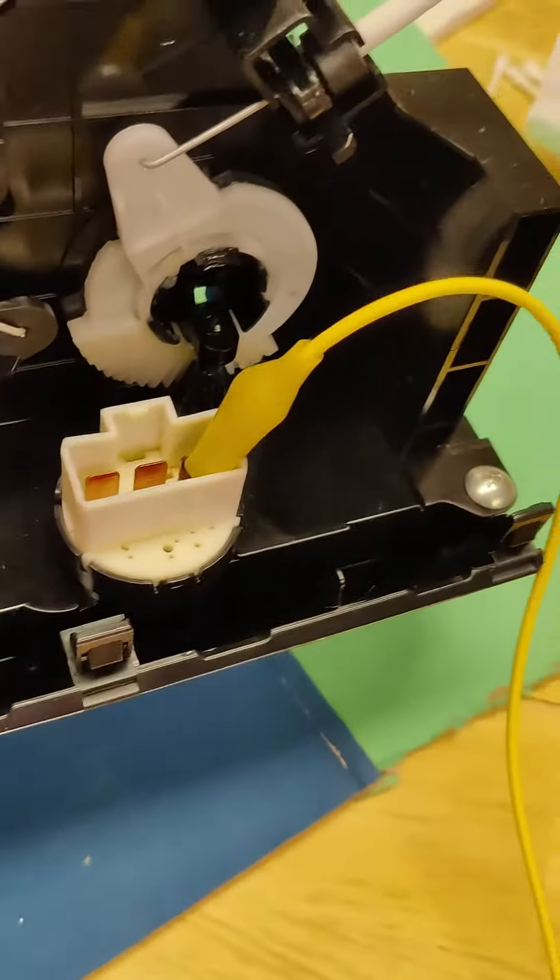But the yellow is on the power pin, and I am now switching it to the first position, like fan position number 1. I'm going to touch the power pin, and I'm able to look at it and see that when it's in 1 it's sending power to load, and that first pin that I just touched also is getting power.